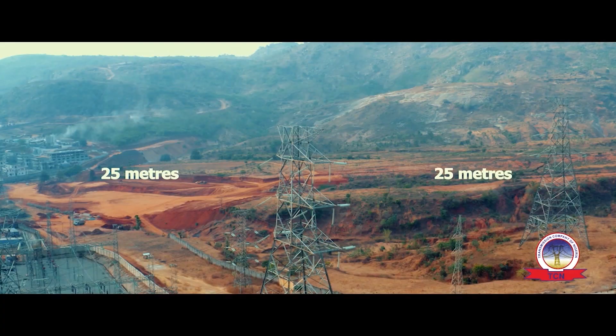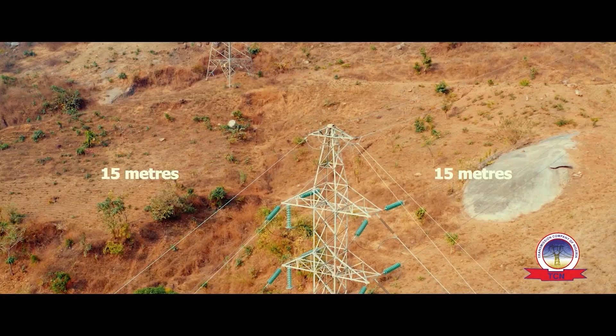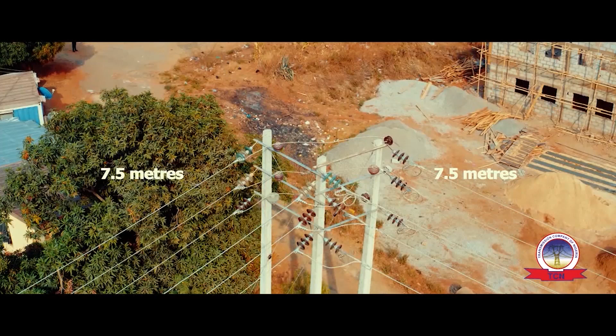Safety compliance means that before erecting any structure around an electricity tower or line, there are safety distances you must adhere to. These are 25 meters on both sides of the tower for a 330 kV line, 15 meters on both sides for a 132 kV line, and 7.5 meters on both sides for a 33/11 kV line. These stipulated safety distances are what we call right of way.